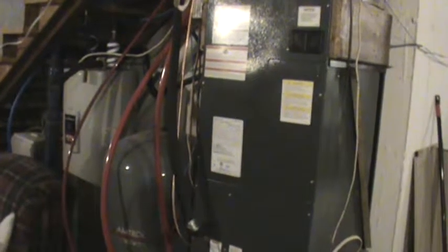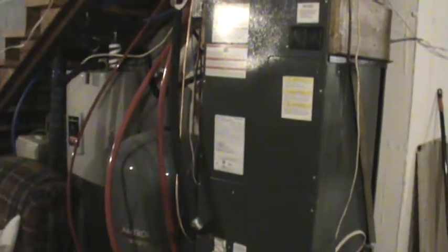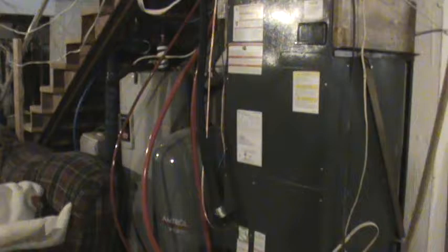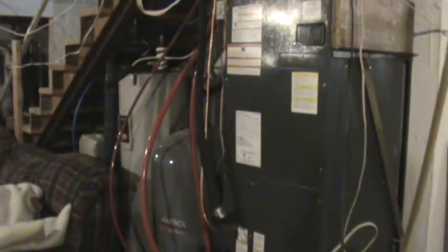So as far as increasing the efficiency of this system, my plan is to convert it to geothermal. So I will still have a heat pump, but my source of thermal energy will no longer be outdoor air. My source of thermal energy will instead be the ground, right? So 55 degrees rather than, say, 20 degrees outside. And in that case, I would be free to run geothermal as much as I like, because I'd be removing thermal energy from the ground, which is consistent year-round. You don't end up with the same problems of frosting and having to run the heat pump in reverse. That really kills the efficiency of an air source heat pump if you have geothermal. So I'm looking forward to doing that.